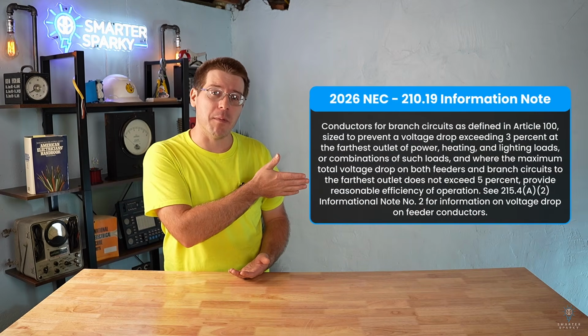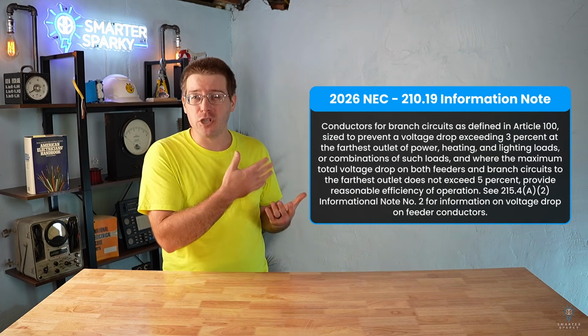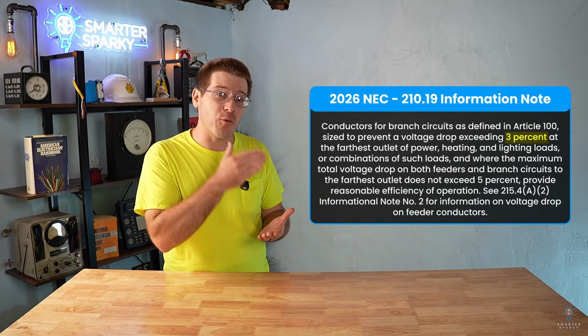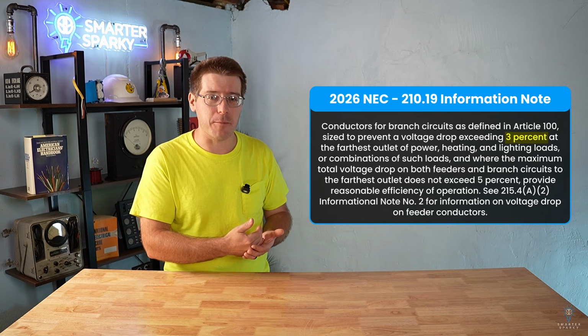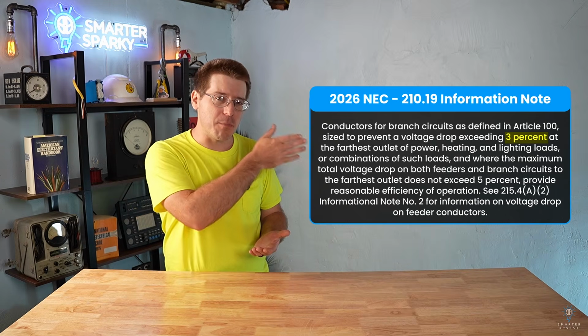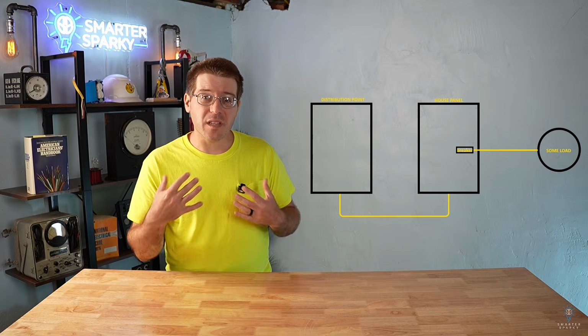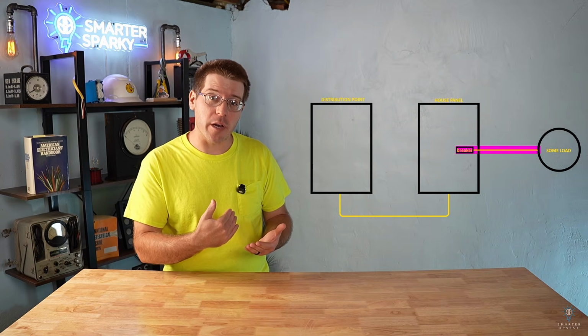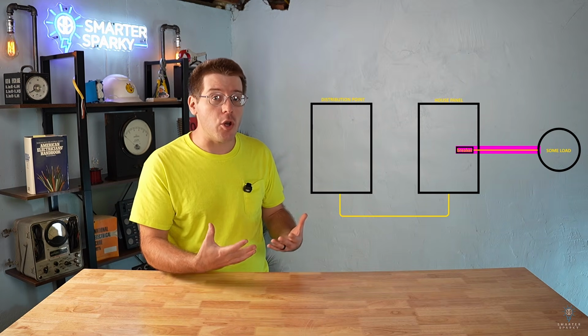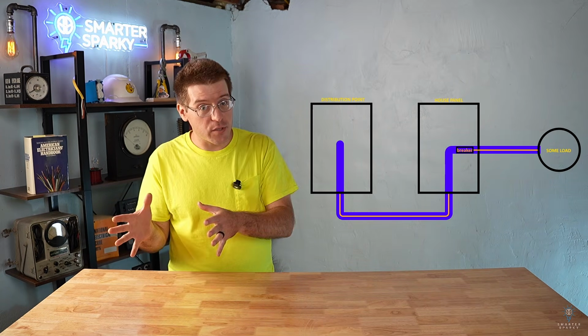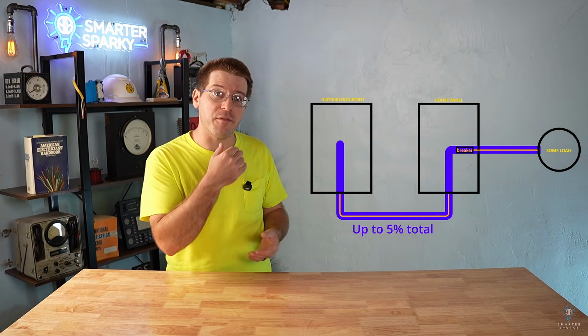The rules for maximum voltage drop can be a little confusing. The code doesn't actually have an enforceable rule for voltage drop, but rather suggests in an informational note that the maximum voltage drop on a branch circuit should be no more than 3%, and from the distribution point to the final piece of utilization equipment should be no more than 5%. What this means is from the actual circuit breaker to the final load should be no more than 3%, and from the service to the load should be no more than 5%.